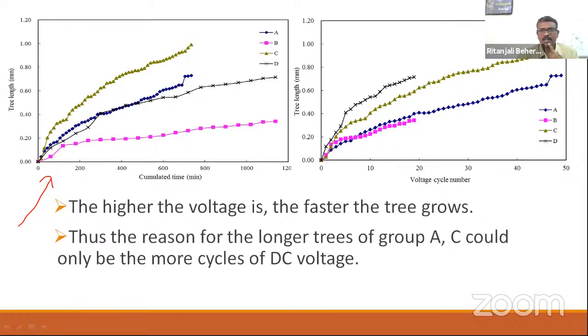The second observation is that the reason for the longer tree length is due to more cycles of voltage application. Here it was about 49 cycles applied, and in the other case 19 cycles, if I remember correctly. So this increase depends on the number of cycles. There are two observations: tree grows due to higher applied voltage, and also due to more number of voltage cycle applications.